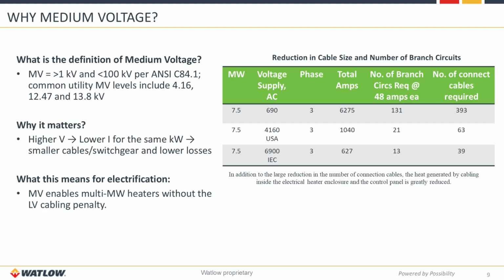So what exactly is medium voltage? It's defined as greater than 1 kilovolt and less than 100 kilovolts per ANSI C84.1. Some of the common utility medium voltage levels include 4.16, 12.47, and 13.8 kilovolts. This matters because higher voltage means lower current for the same power, thus reducing cable sizes, switchgear costs, and resistive losses. This is essential for powering large heaters without massive low voltage cabling penalties.